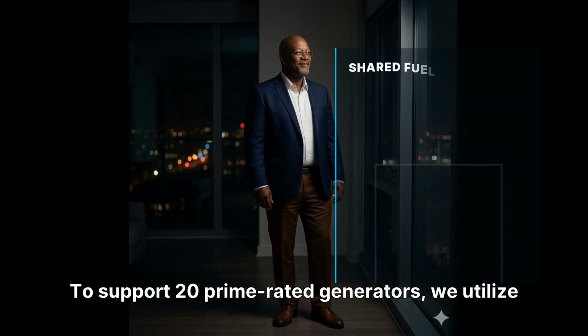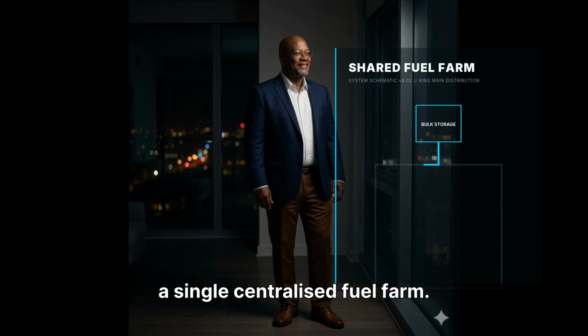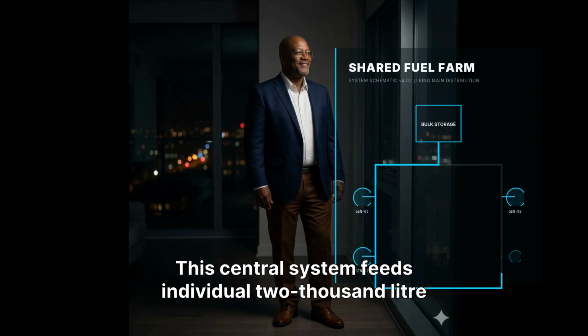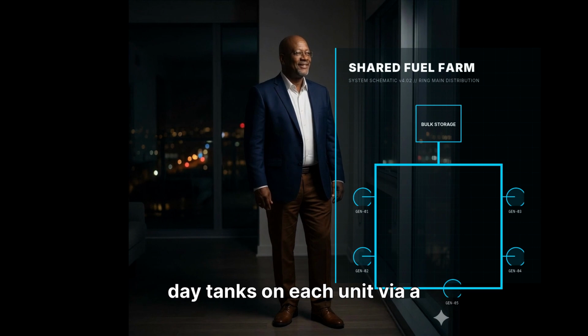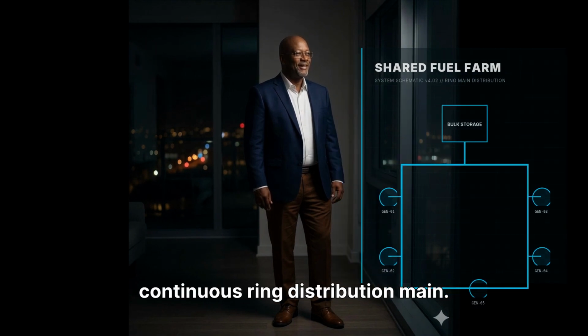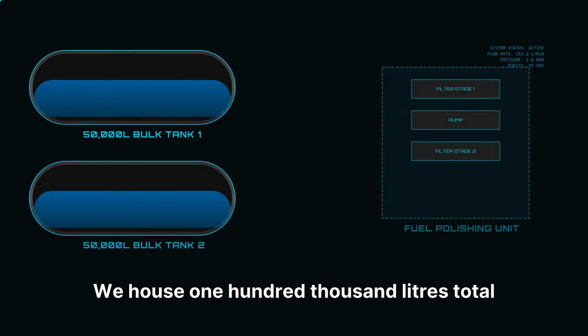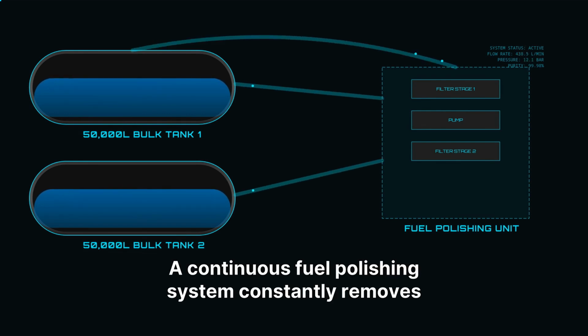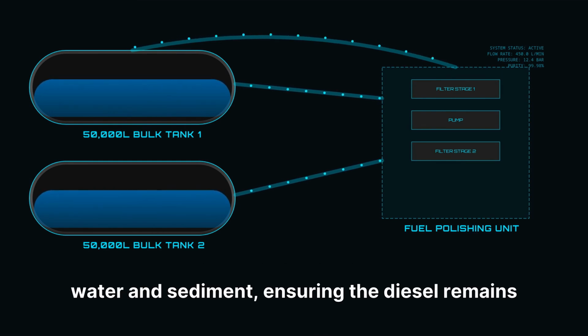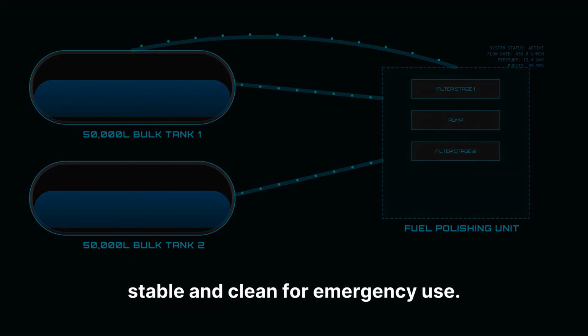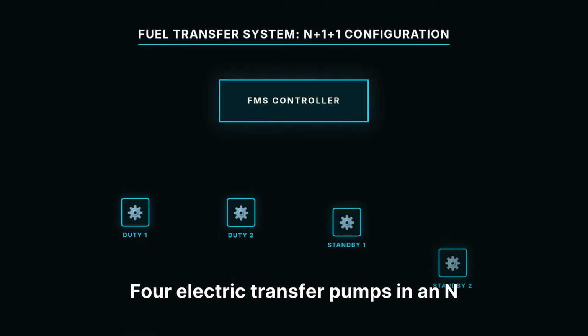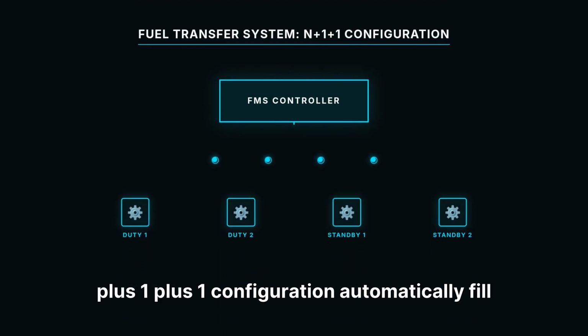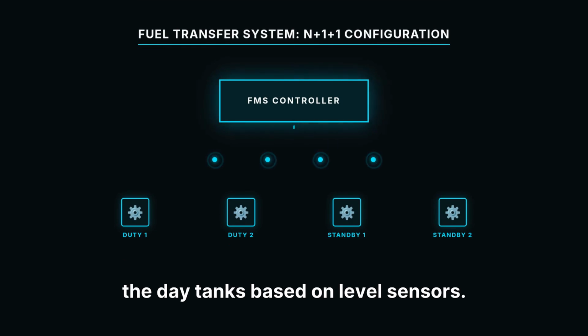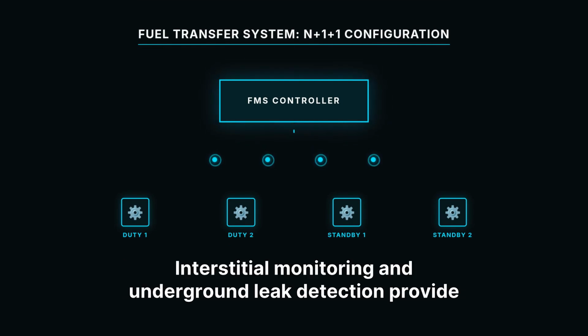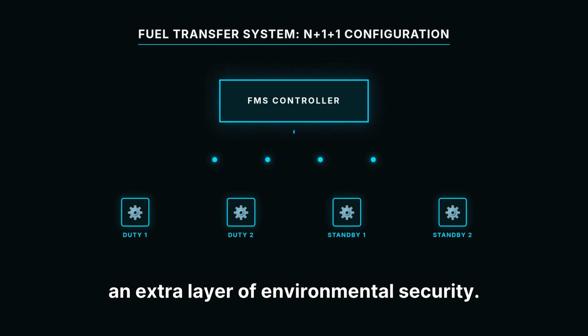To support 20 prime-rated generators, we utilize a single centralized fuel farm. This central system feeds individual 2,000-liter day tanks on each unit via a continuous ring distribution main. We house 100,000 litres total in double-walled diesel tanks. A continuous fuel polishing system constantly removes water and sediment, ensuring the diesel remains stable and clean for emergency use. 4 electric transfer pumps in an N+1+1 configuration automatically fill the day tanks based on level sensors. Interstitial monitoring and underground leak detection provide an extra layer of environmental security.